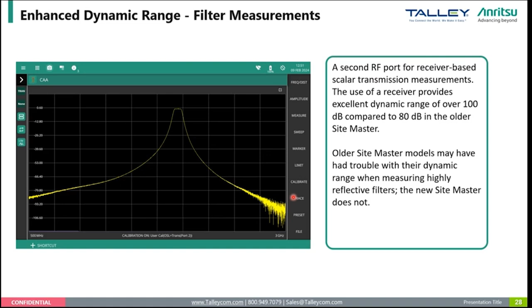Our older instruments, the E series, only had about 80 dB of dynamic range. With our newer instruments, we have close to 100 dB of dynamic range. In the past there were some issues with reflections from bandpass filters, but this is a completely different architecture, and we're able to handle those highly reflective bandpass filters. So if you're doing a lot of filter measurements, this instrument would be great for that.